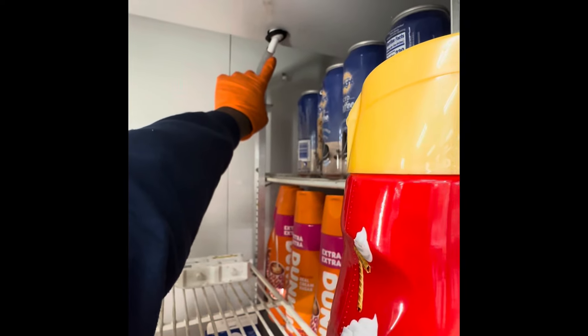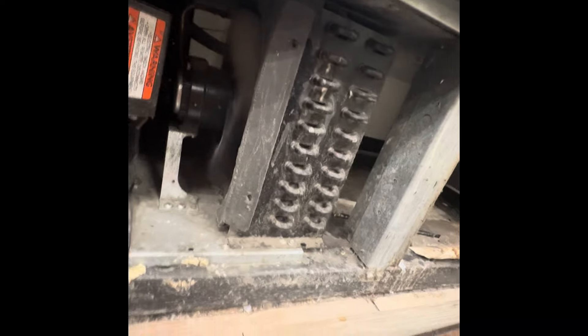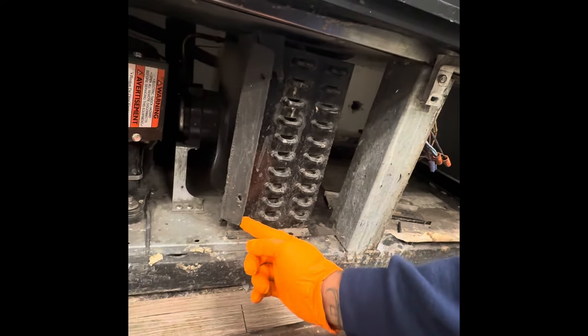I can also see that we've got a drain issue right here beneath the cooler. The drain is plugged. The evaporator condenser fan is running, and we could use a new shroud.